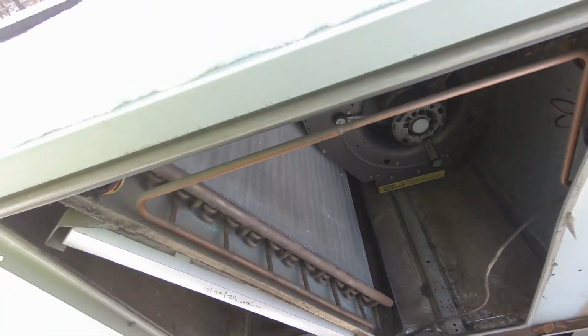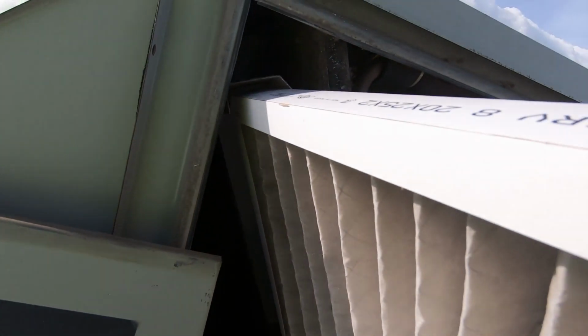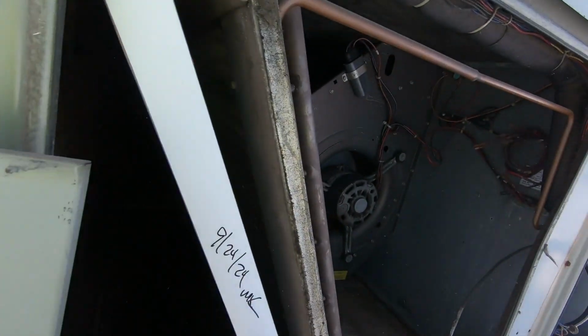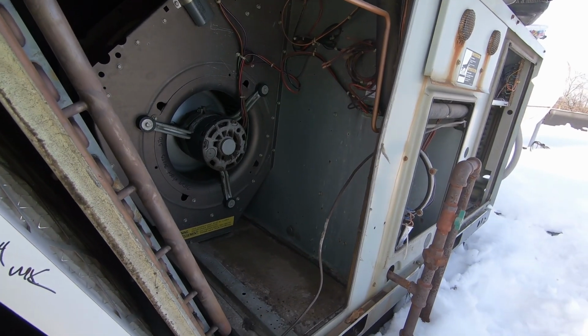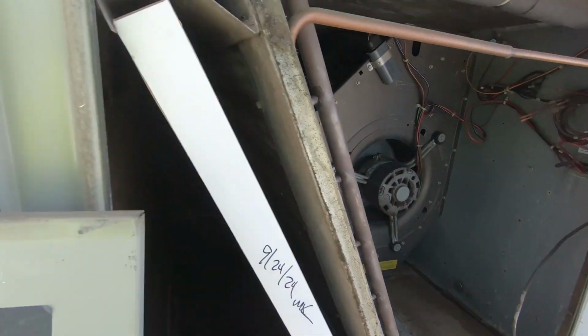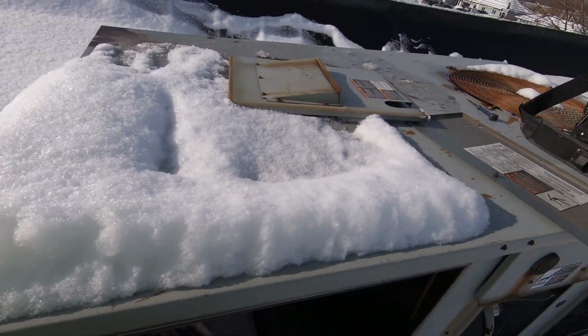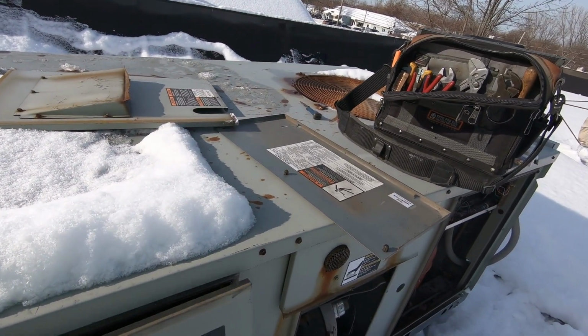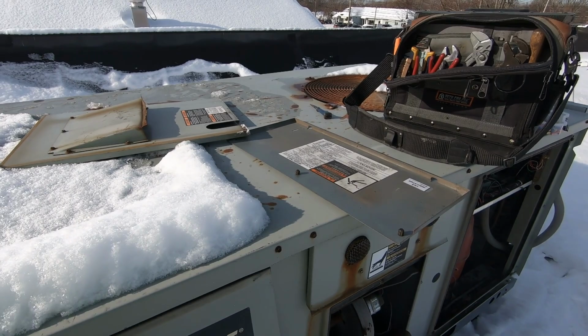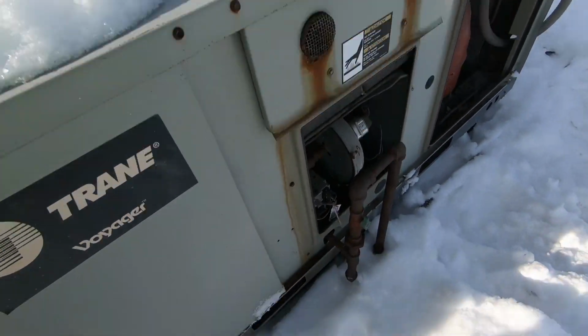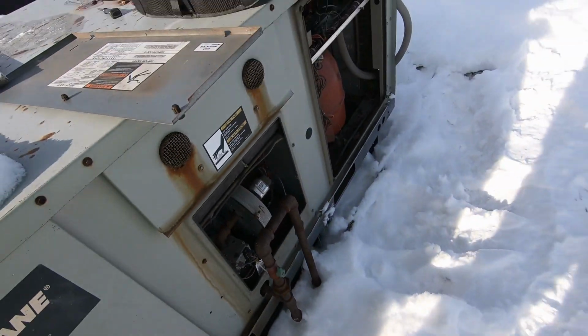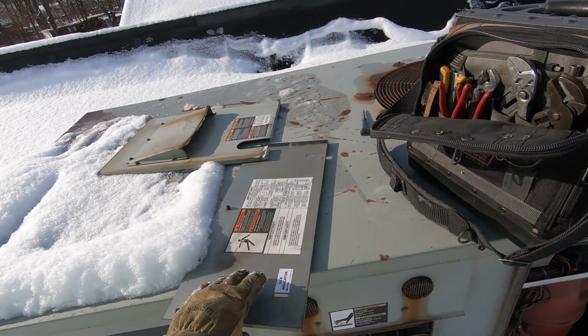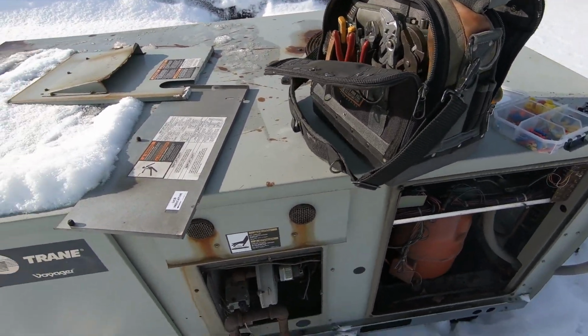Direct drive. Let me get these filter sizes because they're gonna want to know. Two 20 by 25 by 2s. Let me write that down before I forget. Blower was running, so I'm assuming everything is good there. Get this panel put back in place, test this igniter, and then we'll recycle if it's good and see what the deal is. All right, let me put the camera down, get my meter out, and we'll go from there.